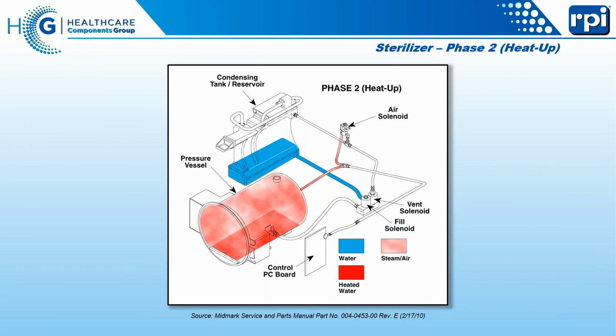Another thing that affects these sterilizers, and a lot of other medical equipment, is you can't put one of these on a GFCI. They hate GFCIs. And the reason for that is the heating element. A GFCI measures leakage current to ground. And when you have a hot wire going through a ring of grounded metal, you're going to develop leakage. So the older that heating element gets, as it tends to fade over time, it will sag, and it will actually become closer to the wall of that tube that it's in, and that will cause all kinds of problems with GFCIs.